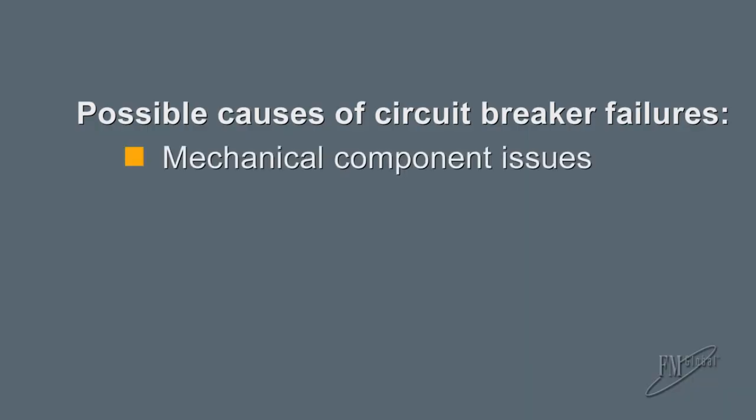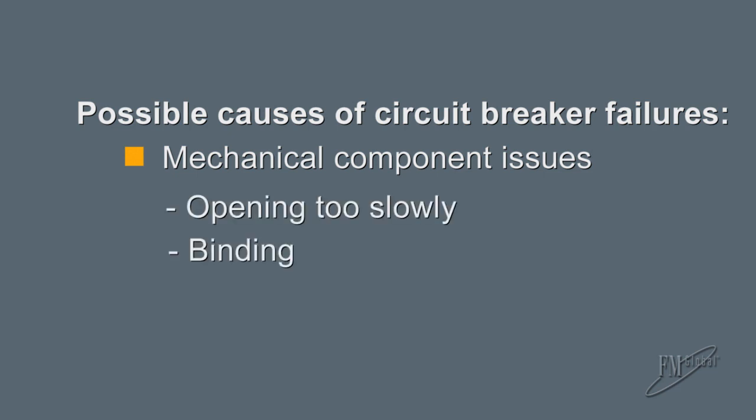So what causes breakers to fail? Let's consider a few of these causes. The most common is related to mechanical component issues resulting in the breaker either opening too slowly, binding, or not opening at all.